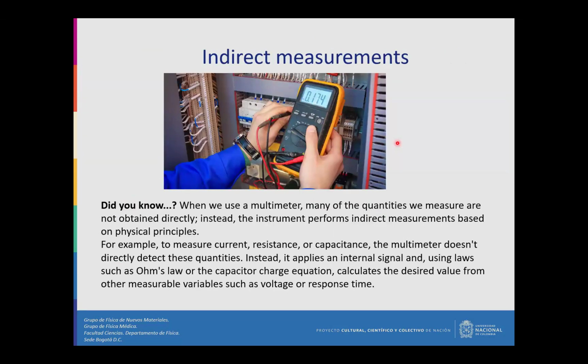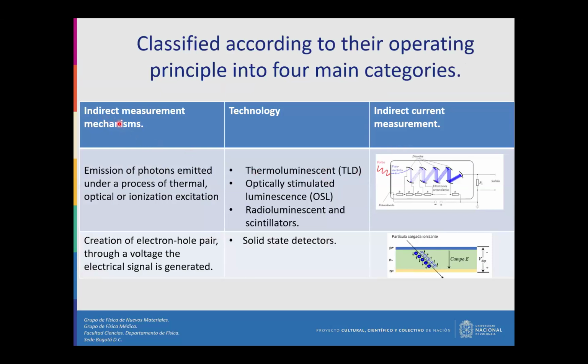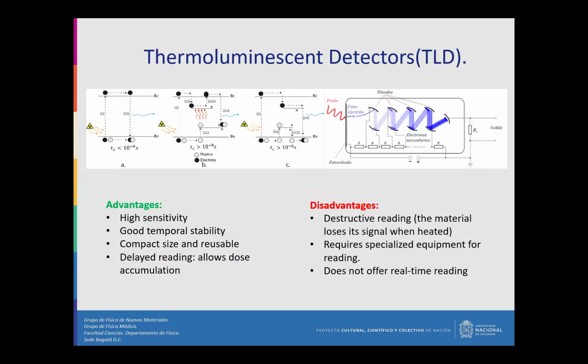So if we come back to this part, we see the measurement mechanism in these four technologies really is the emission of photons under a process of thermal, optical, or ionization excitation. And we need a photomultiplier to convert that photon into a current signal. In the case of the solid state detectors, we have the creation of electron-hole pairs, the same mechanism that we have here. But in this case we don't need the electron-hole recombination. What we need is to take that electron and that hole, move them out of the material, and take that signal. So we have here a current from the creation of electron-hole pairs, and we have the emission of photons from the recombination of the electron-hole pair. Okay, that's so important to note in this case.